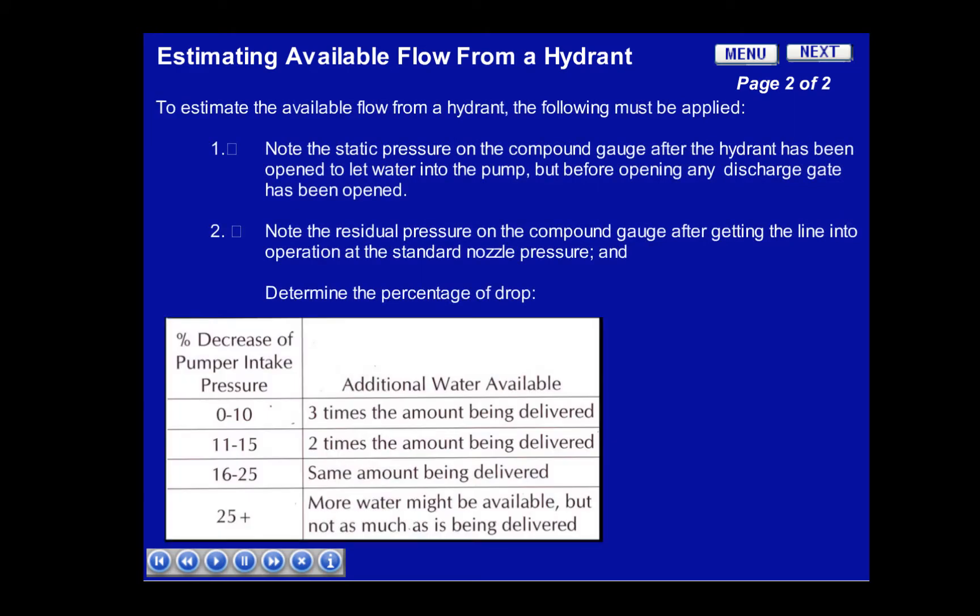To estimate the available flow from a hydrant, the following must be applied. Note the static pressure on the compound gauge after the hydrant has been opened to let the water into the pump, but before any discharge gate has been opened. Then note the residual pressure on the compound gauge after getting the line into operation at the standard nozzle pressure, and this determines the percentage of the drop.